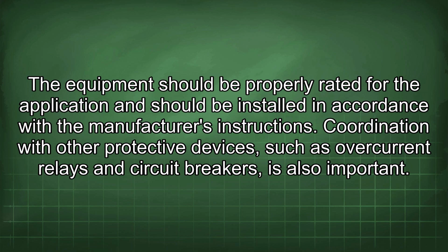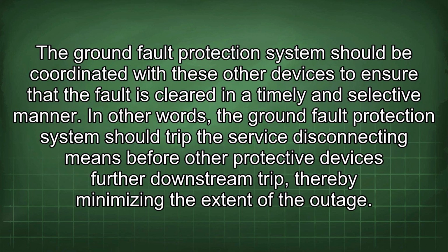Coordination with other protective devices, such as overcurrent relays and circuit breakers, is also important. The ground fault protection system should be coordinated with these other devices to ensure that the fault is cleared in a timely and selective manner. In other words, the ground fault protection system should trip the service disconnecting means before other protective devices further downstream trip, thereby minimizing the extent of the outage.